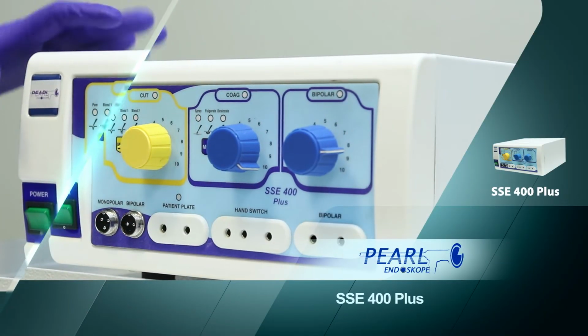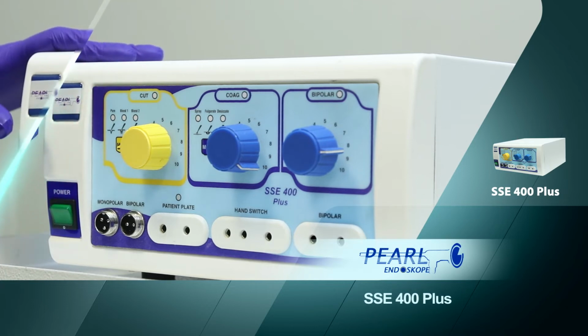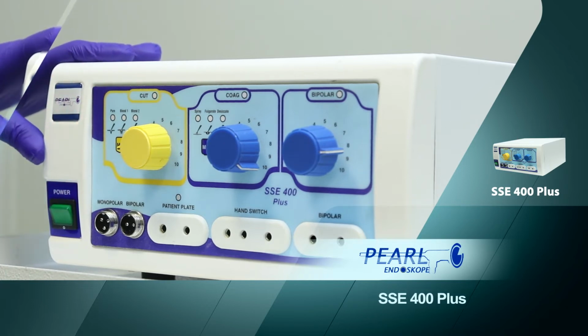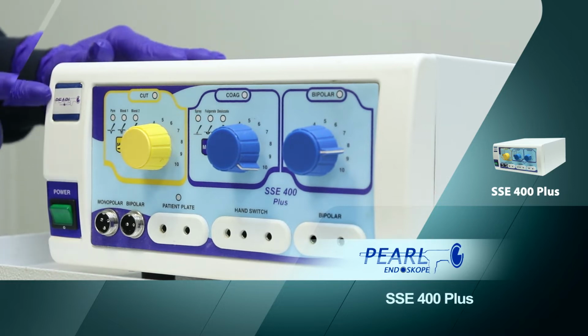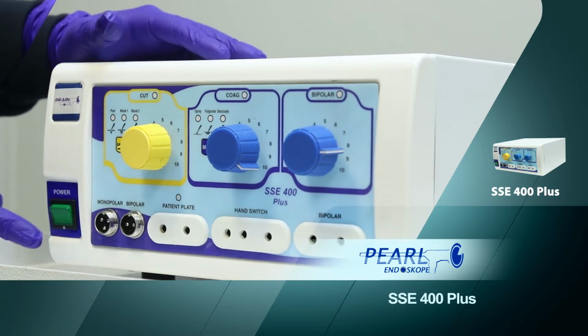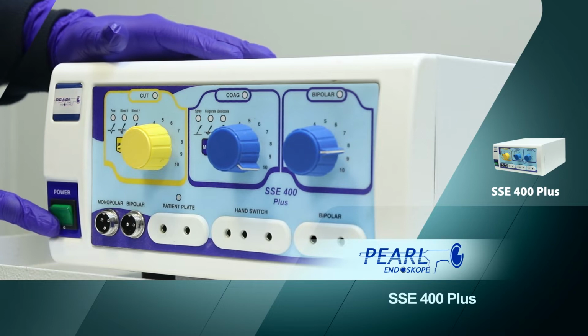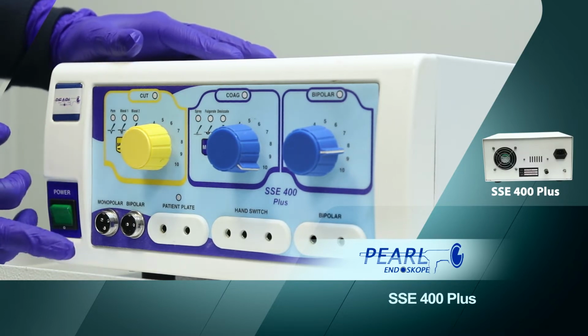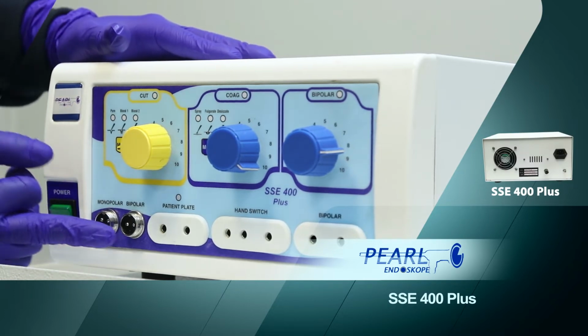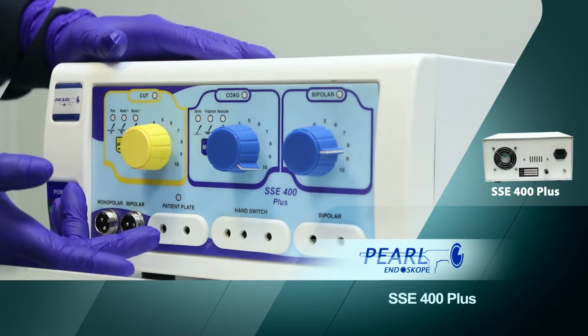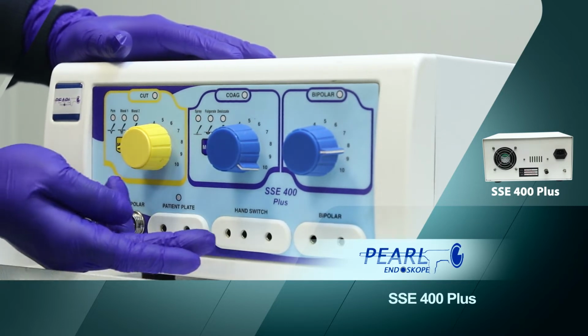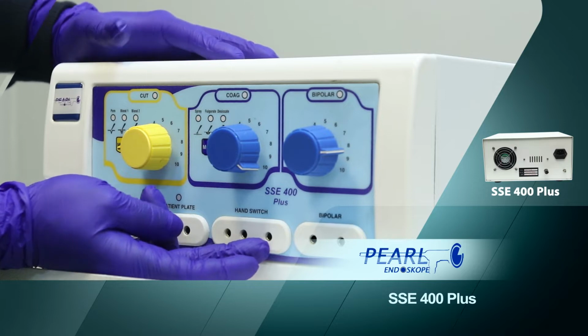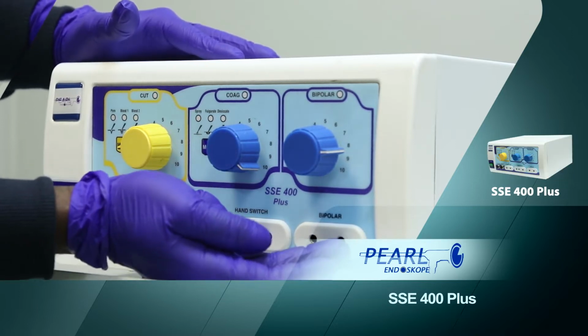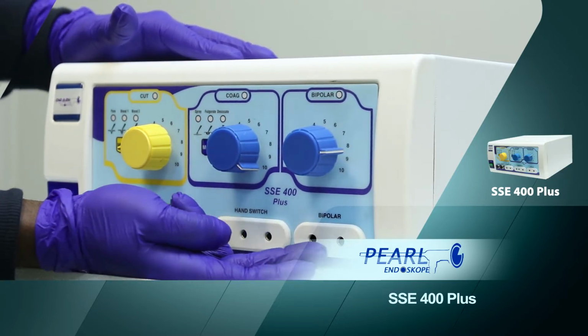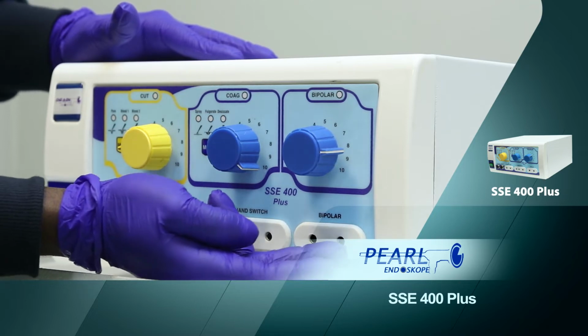This is the SSE 400 Plus for surgical diathermy. This is the power switch here. This is the monopolar foot switch connector, the bipolar foot switch connector, the patient plate connector, the hand switch connector, and the bipolar connector for bipolar hand instrument and bipolar cord connector.